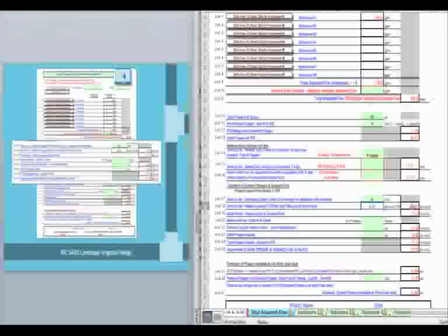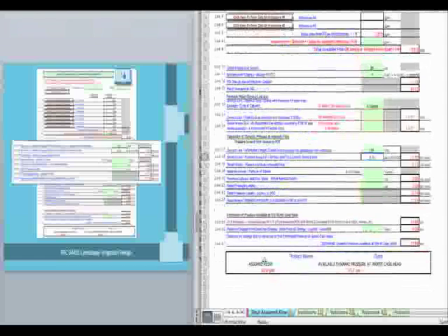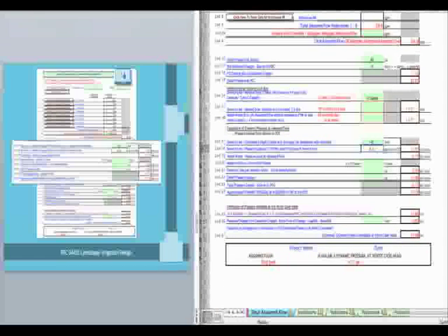So what is happening in this section of the worksheet is it adds what we do have, which is pressure loss through the service line and meter, and you end up with a total pressure loss of 6.14 and an approximate dynamic pressure at the assumed flow that we calculated up here of 77.13 psi at the point of connection. Now we're not quite finished yet.